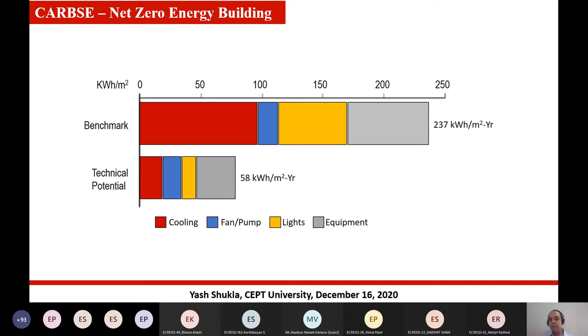And this is a metric that's typically used in energy consumption to compare different buildings, because the larger building will take more energy and the smaller will take less energy. To neutralize that, you divide by the area in meter square and then see what is the annual energy consumption for that building. So our benchmark was 237 kilowatt hour per meter square per year. And then we said if we put together all the things that we know about the efficiency of the cooling systems, the fans, the lights, and the best research equipment, we can reduce that to our target of 58 kilowatt hour per meter square per year, or 58 EPI, energy performance index. So that's called the technical potential that we wanted to achieve, from 237 to 58 kilowatt hour per meter square per year.